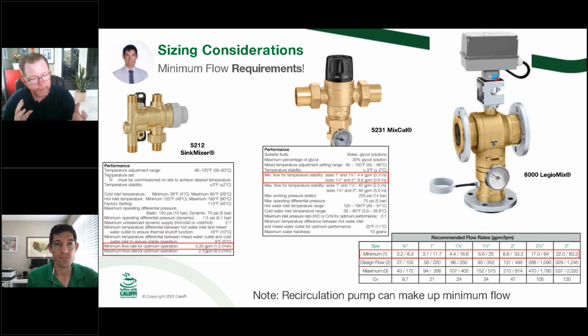Yeah, it comes back to that discussion, Max, of you'll look at it and you'll see, oh, well, it's an 1.25" line, so I'm going to put an 1.25" LegioMix in this, or a 1.25" MixCal in it. We have this conversation over and over again. We don't care what size connections are there, what size piping is there. We care about what the min, max and the design flows are that we're trying to achieve. Yeah. You can very easily oversize a mixing valve for the application, which we see quite a bit. Yeah, and of the questions you posed at the beginning, what is the existing pipe size is potentially the most misleading, where some of the other factors are more important. And the biggest one is knowing what your max flow rate is and using a calculator if it's an existing building to figure it out, because it could be a 3-inch pipe and you need a 1.25" valve for the actual load because it was oversized.